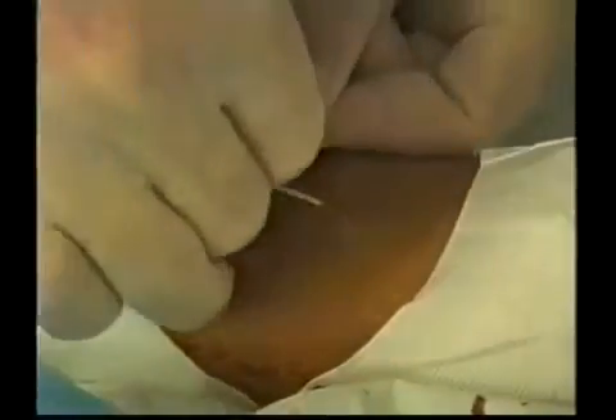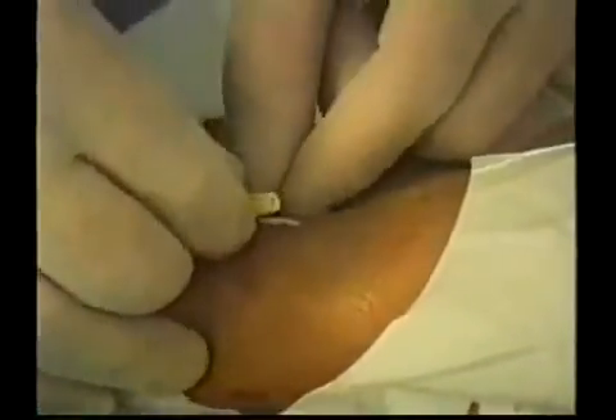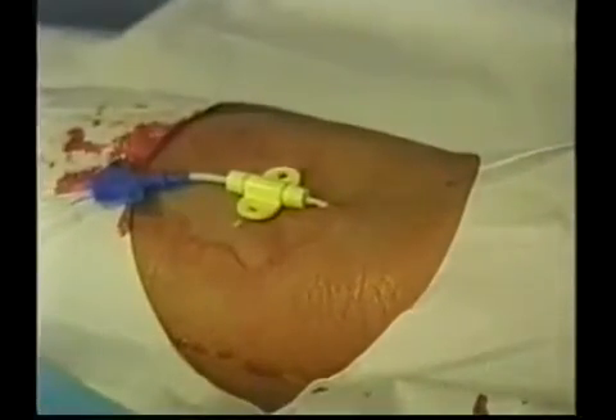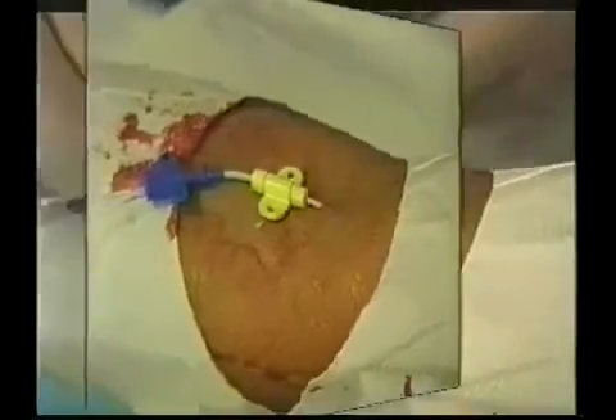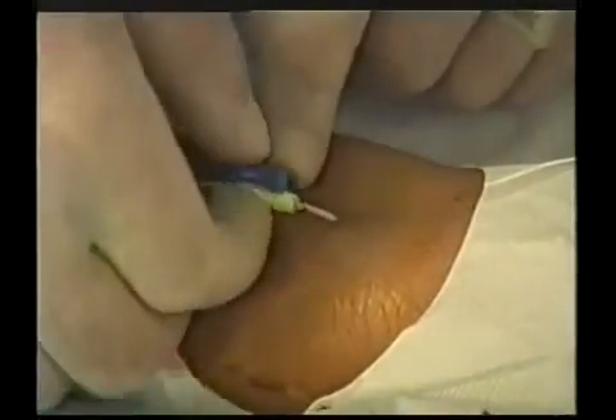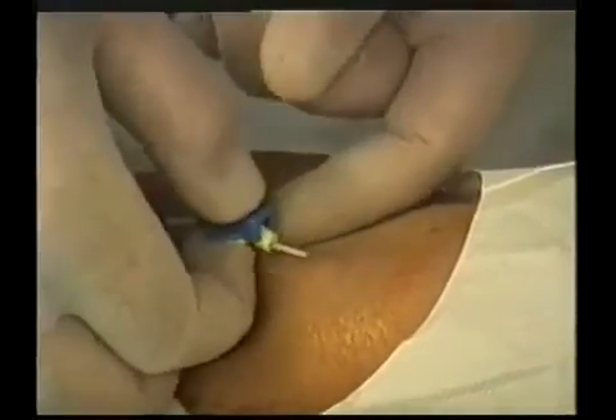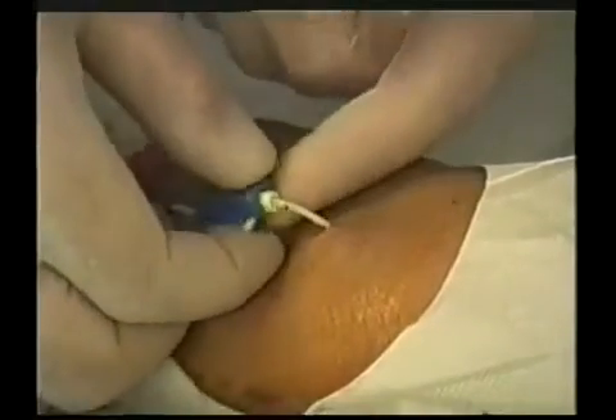If the catheter and box clamps are needed for catheter securement, they are attached by placing the yellow catheter clamp over the catheter approximately 3/4 to 1 inch from the insertion site. The blue box clamp fits over the yellow catheter clamp to make a snug fit and secure the catheter.